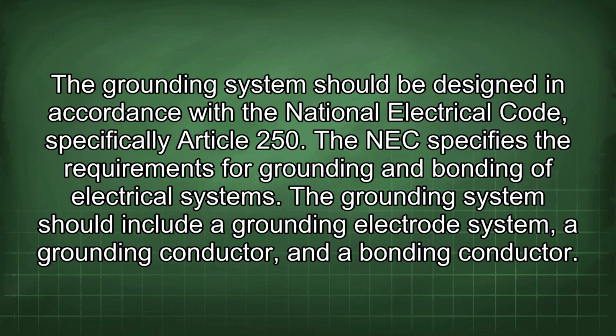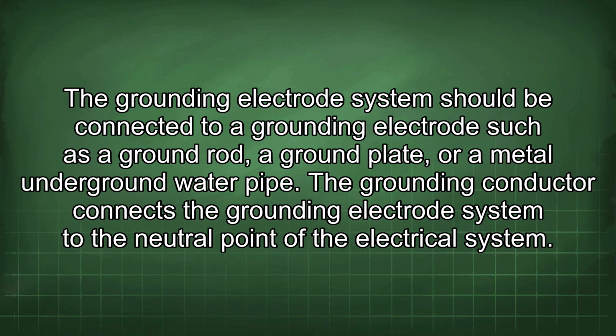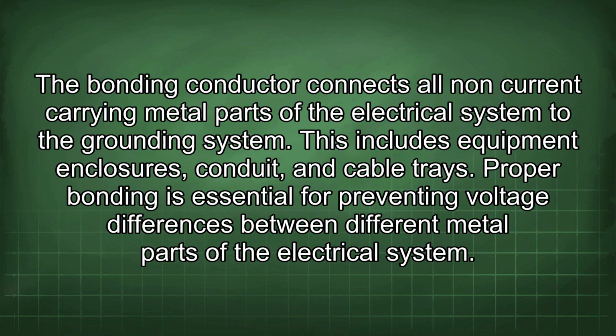The grounding system should include a grounding electrode system, a grounding conductor, and a bonding conductor. The grounding electrode system should be connected to a grounding electrode such as a ground rod, a ground plate, or a metal underground water pipe. The grounding conductor connects the grounding electrode system to the neutral point of the electrical system. The bonding conductor connects all non-current carrying metal parts of the electrical system to the grounding system. This includes equipment enclosures, conduit, and cable trays.